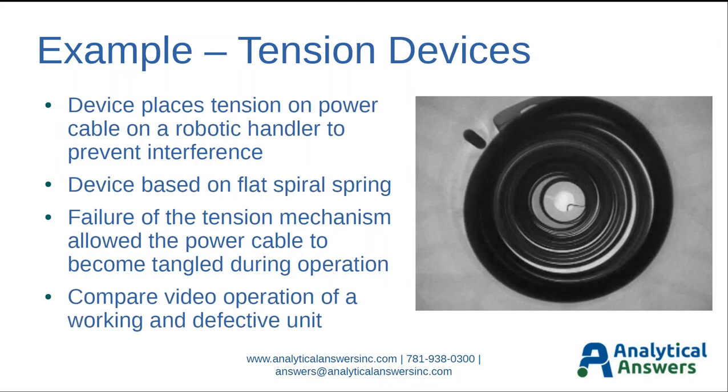Let's go on to something a little more serious. Here we have a tension device where you have a flat spiral spring. This device basically has a hub around it and as the hub rotates you increase the tension on the spring. By having a cable on that hub it's designed to place tension on a power cable on a robotic handler to keep the cable out of the way of the mechanism so it doesn't get tangled. The failure of the tension mechanism allowed the power cable to become tangled and that was very bad for both the piece of equipment and anyone that was nearby.